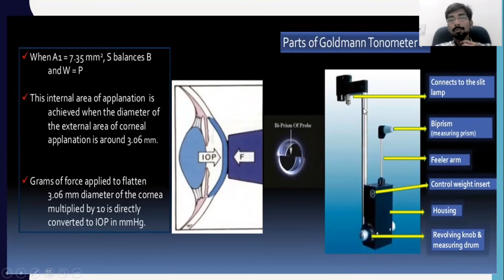These are parts in the Goldmann tonometer. Procedure: the instrument is mounted on the slit lamp. Examiner's view is directed through the center of the biprism. Biprism is attached by a rod to a housing. Housing contains a coil spring and a series of levers that are used to adjust the force of the biprism against the cornea. Two beam splitting prisms within the probe optically convert the circular area of corneal contact into two semicircles.